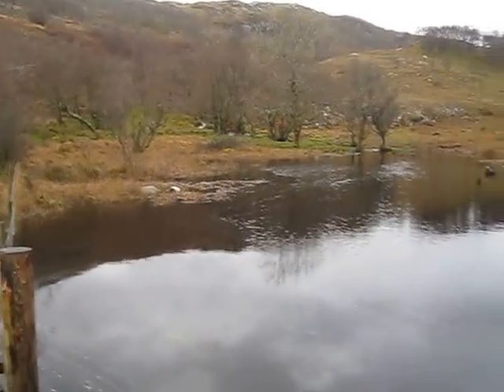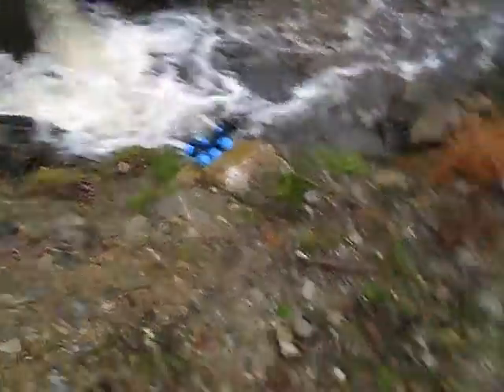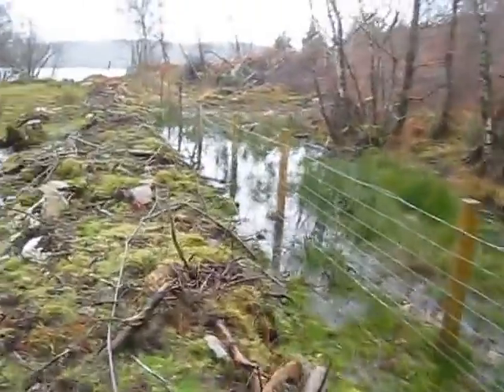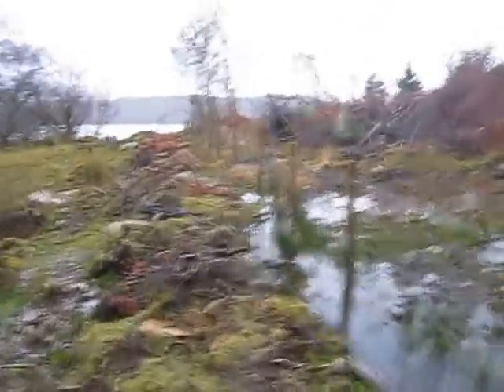We haven't really harmed the river — there's still plenty of water in it. The other interesting thing is we used three pipelines underneath through this dam. There are three pieces of pipe, and the intake valves are underneath these lids. The three pipes go down the hill, and there's the compensation flow which tees off back in the river. The compensation flow pipes also act as anti-vacuum, so if we do turn those main inlet pipes off, air can go in those pipes and you can drain your pipeline.